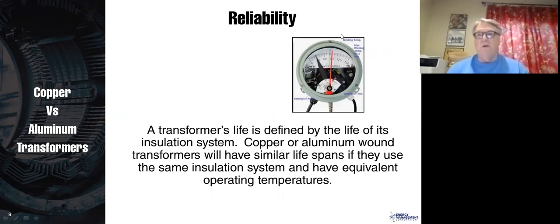Next is your reliability. What determines the reliability of the transformer? Well, mostly reliability is determined by the insulation system and how hot you run the transformer. So the better your insulation, the higher the BIL rating, that's your basic impulse insulation level, the longer that transformer is going to last and the better it's going to withstand surges from the line. The hotter you run the transformer, obviously, the lower the lifespan of that transformer. Well, you can use the same insulation system, you can use the same heat rises in a copper or aluminum transformer, and therefore there's really no advantage to one or the other.